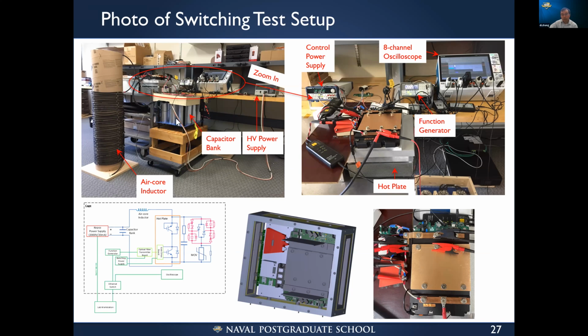So when we do it, we just pre-charge the capacitors, then turn on the devices and create a short circuit, right? And to cut the fault current. So this is the test setup where we're doing right now with the right devices, the bus bars, and almost the same layout as in the mechanical designs: MOVs, the snubbers, the thyristors, and also the passive trigger circuits.